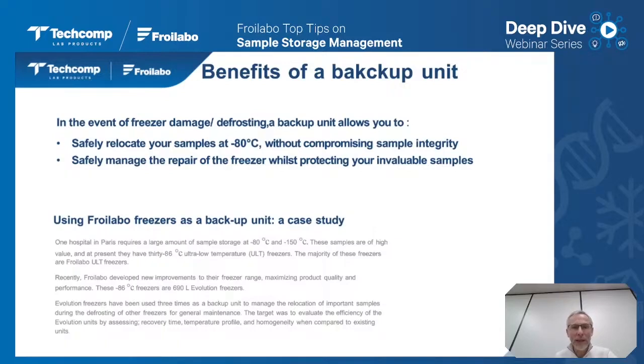When we speak with people about the yearly maintenance, they have to defrost the unit completely. To do it, they need to have a backup unit. A backup unit is extra equipment, an extra ultra low temperature freezer. It can run just before starting the yearly maintenance on one unit. Using a backup unit generates strong benefits because you will be sure that you can safely relocate your samples at minus 80 degrees without compromising sample integrity.